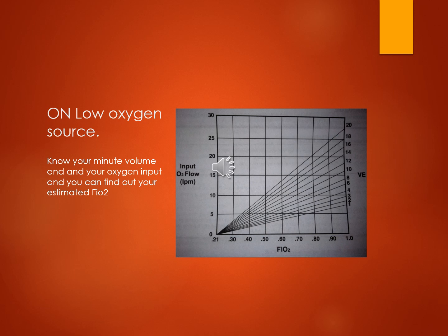If you look on this, this is your low oxygen source. And remember, you press that button to switch it over to low oxygen. You put your Christmas tree on there. You have your O2 tubing hooked up to your flow meter, and you're running your flow. You're going to look at the minute ventilation that your patient is generating on the ventilator. If I'm looking at the minute ventilation and it looks like I'm going to say 10, and I want an FiO2 of 80, my old eyes are looking like that is going to be somewhere around 15 liters. That's what I would generate on that. So do I put 15 liters on? That should give me about 80% FiO2 for that patient. So it's general. It's not perfect, but it's a graph that they put on there. So hopefully that'll help us out.